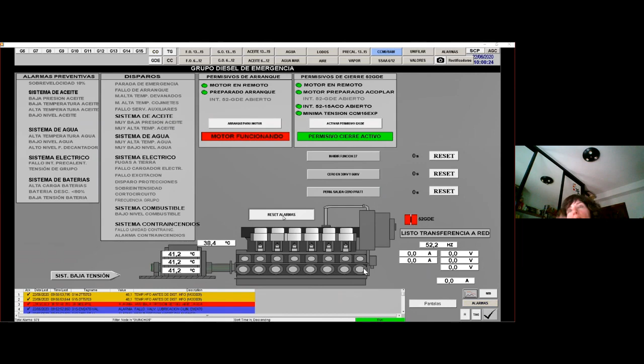So now we have our emergency diesel started. What we have to do now is reset alarms and check that the group switch is closed. It closes automatically, and now we have to restore the voltage in the electric bars.